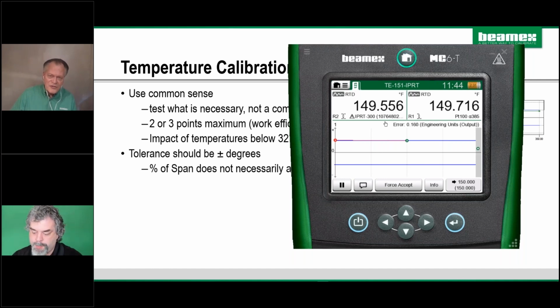So one of the things about doing these offsets is even though this is off by half a degree, if you put an offset into the control, you're getting a true temperature. So you can do some really cool things by making these kind of adjustments, especially if you've got zone control. If you've got 6 zones, you want all those zones reporting the same temperature to the control room, so that if it impacts your quality, you could raise the temperature a little bit in zone 1 and drop it in zone 6 where it impacts the quality of your product. Yep, great point. So using the dry block, you can do some really cool things because you are getting very close to the true temperature.